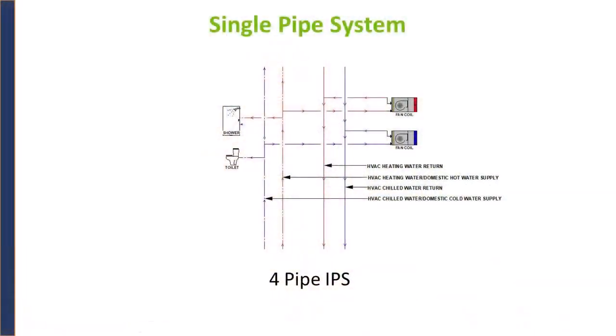So what if I did an integrated piping system? Here I'm going to use the domestic hot water pipe as 2 pipes in that 4-pipe. On the left, we're going to use the hot and cold water pipes as the supply mains for that 4-pipe fan coil, and then we're going to have a 2-pipe return. So I went from 7 to 4. That's pretty cool, huh?